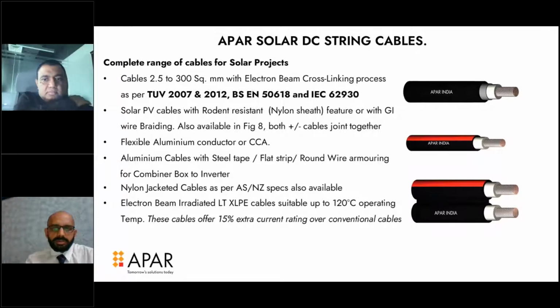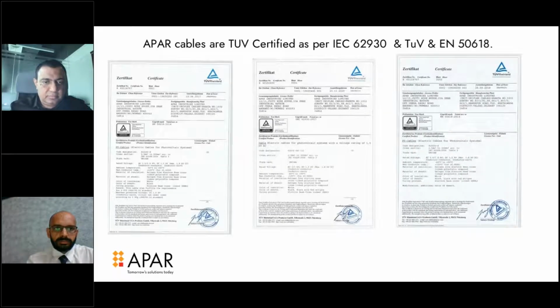With the rising copper prices, there are different options that we go with. The underground cables can be with either steel tape armoring, a flat strip, or even round wire armor for the combiner box to the inverter. These E-beam cables are suitable for 120 degrees operating temperature, and they offer nearly 15% extra current rating as compared to our conventional cables. These are the certifications that we have for 62930 as well as for EN 50618.